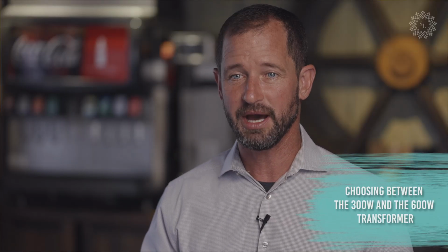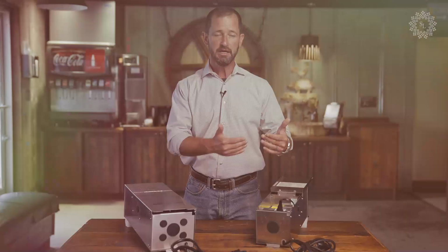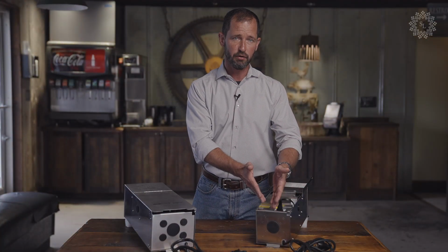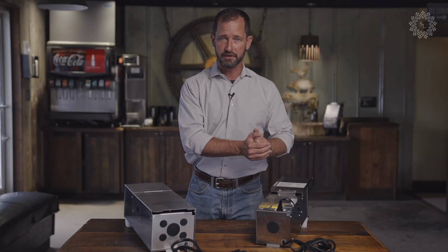The reason you would choose the 300 or the 600 is the size of the system and the amount of energy you're using. We always have the general rule that you never run your transformer over 80% capacity, but it's so important to have an amp meter to test it, because if you have long wire runs, you're going to have more resistance on the wire and your amperage is going to go up higher. So test the low voltage side and the high voltage side.